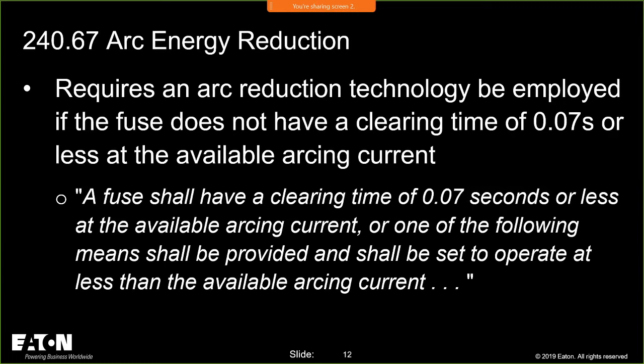So I showed you that 1584 calculates a maximum and minimum arcing current, but the code doesn't say have a clearing time of 0.07 seconds or less at the minimum available arcing current or maximum available arcing current. So technically, I could use the higher number and get away with it, but from an engineering perspective, my guidance is I'm a conservative person. When it comes to engineers, we're supposed to be conservative from a safety side. That lower arcing current is what you want to use.